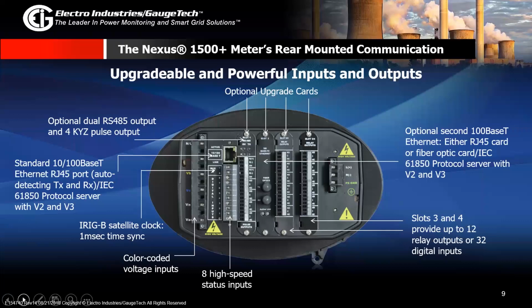All you have to do is get one of these option cards from us, and then you just take the 2 screws out, one screw at the top, one at the bottom. You just slide one of the cards out, or if you have an empty slot already, you slide the new card in, and now the meter has the new communication capability. So this makes it a really simple field upgrade for future proofing your system down the line if you have new communication options that you want to add to the meter. It also comes with the Ethernet options, the RS-485 standard options that you can use to connect to your meter. It also has an IRIG-B satellite clock for up to 1 millisecond time sync. And you can choose to have relay outputs or digital inputs into your meter.